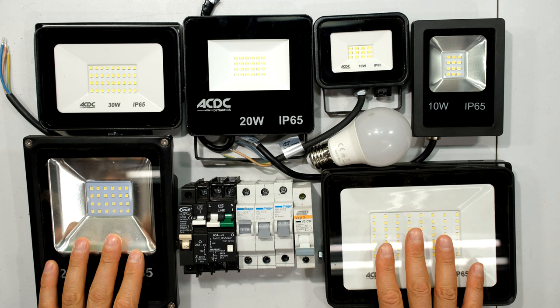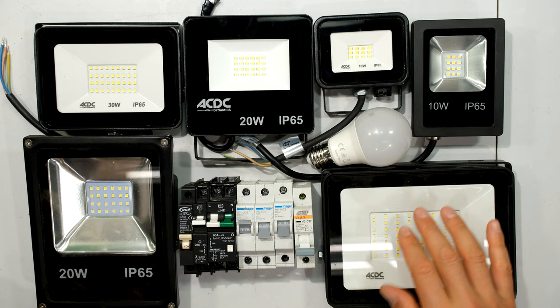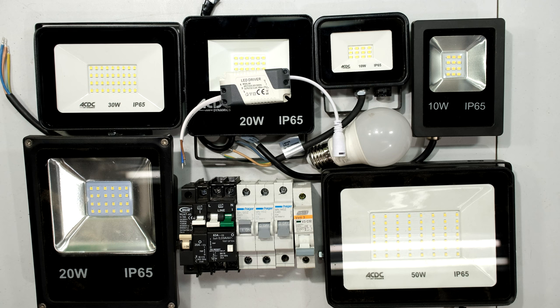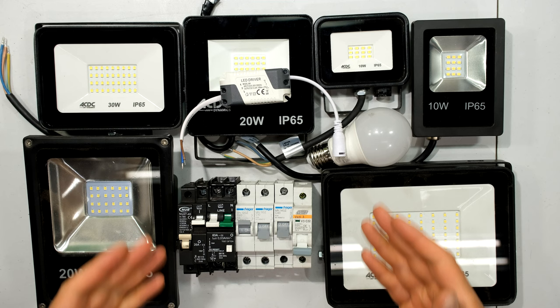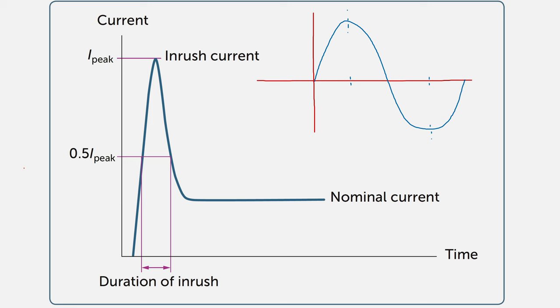In this video I'll be explaining LED floodlights and circuit breakers. Many people like using LED floodlights because they use a significantly lower amount of energy for the amount of lumens. Inside the LED floodlight there is an LED driver circuit, and that driver circuit often has a high inrush current. That inrush current becomes a problem when selecting circuit breakers and limits how many LED floodlights one may connect to a certain circuit breaker.